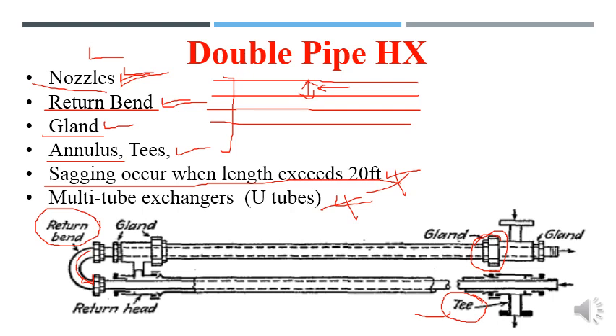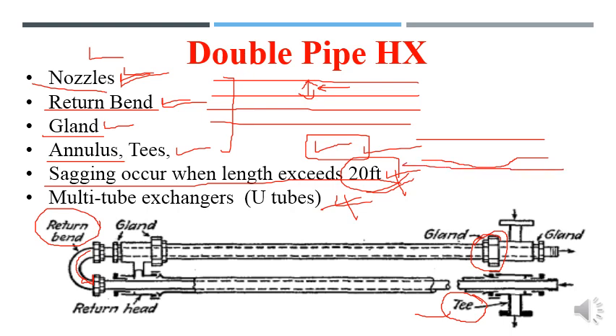When the pipe sags, the inner pipe moves downward and touches the outer pipe, disrupting operation and the annular flow. Therefore, the length of the pipe is generally kept to a maximum of 20 feet. In applications like distillation, double pipe heat exchangers can be used, but they usually require larger area, meaning more hairpins and more space.